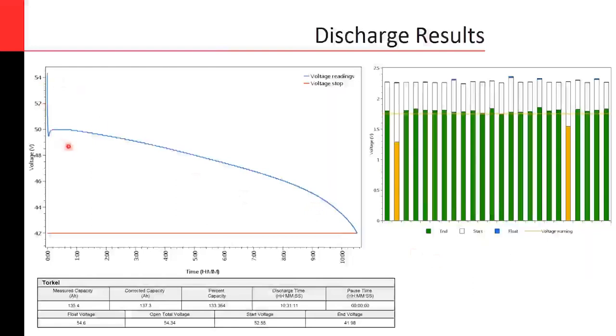So in this case, it is a 48 volt battery, which running the discharge down to 1.75 volts in 24 cells, the stop voltage is 42 volts. So this is why we have this red line here. And this test was programmed to be an 8-hour test. In the end, it ran for like 10 hours and a half. So the capacity obviously is higher than 100%, and you can see that calculation here. The percentage capacity is 133%. Very good result. You were just expecting 100%, but you have 30% more of battery there.